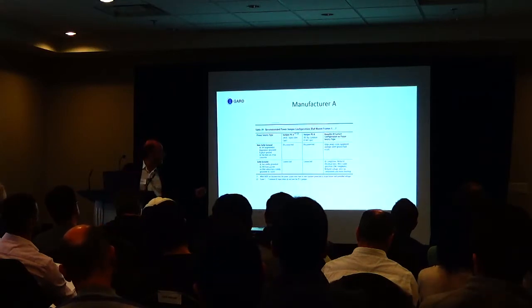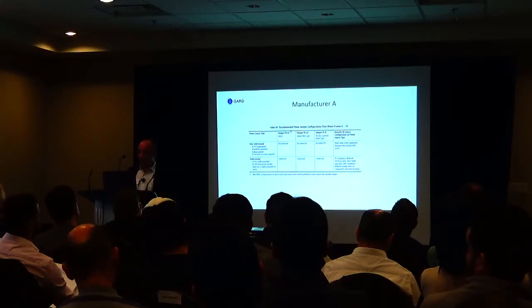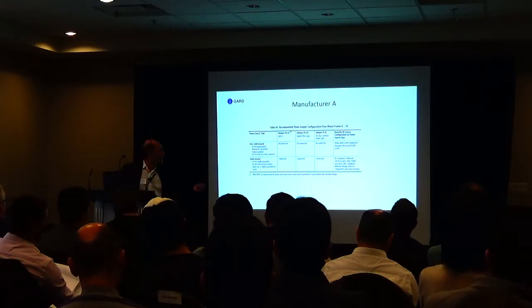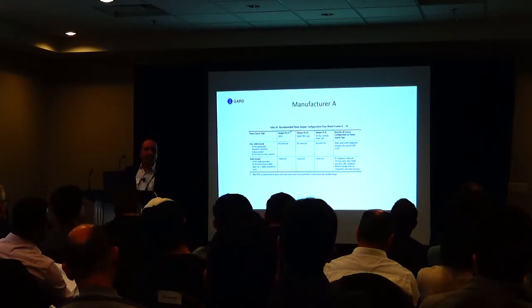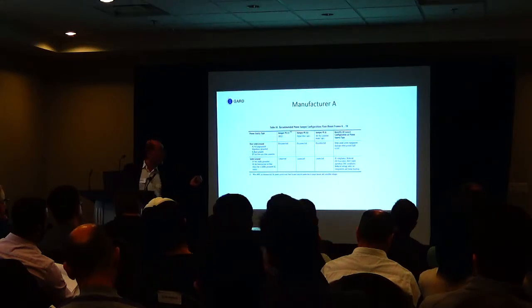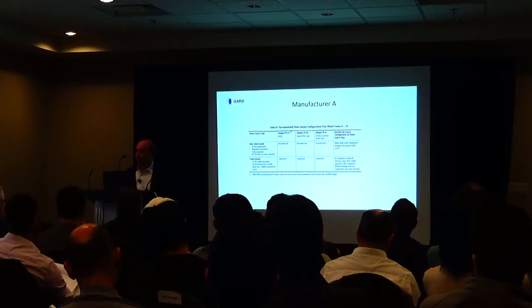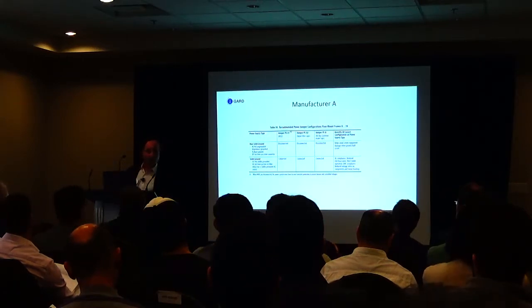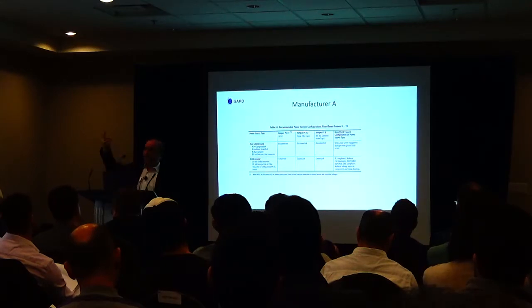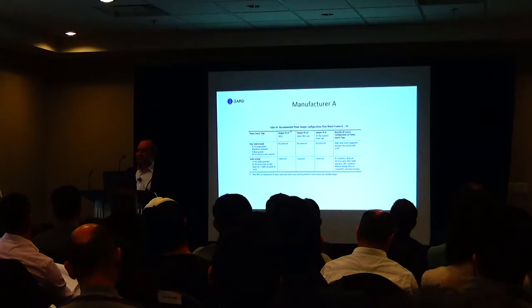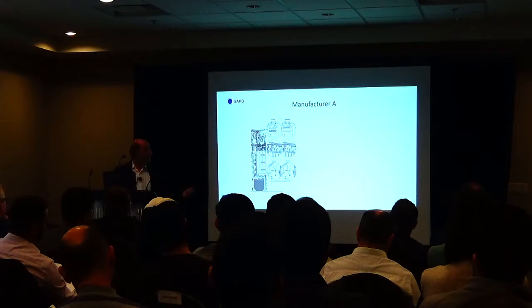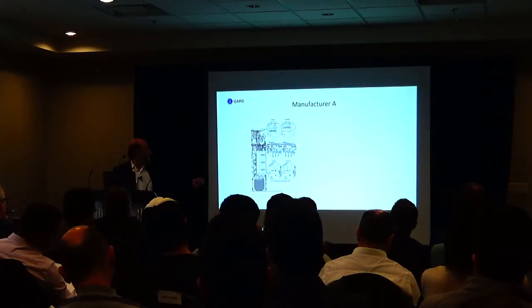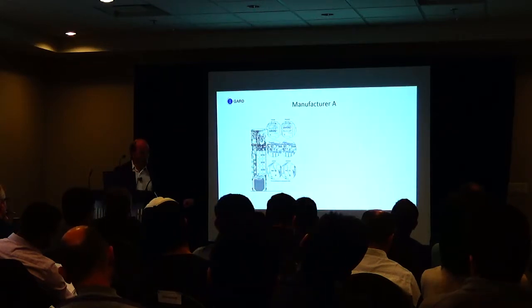And the DC bus mode caps. Same manufacturer, 3 jumpers this time. MOV, always have to disconnect the MOV because the MOV is not compatible with a B-phase grounded system or when 2 of the phases are elevated in potential. And that's what happens when you have an ungrounded system or a resistance grounded system. 2 of the phases are going to be elevated. Not always A and C. Sometimes it could be A and B. Sometimes B and C. And they even show you where the jumpers are. Connected, disconnected. Connected, disconnected. Connected, disconnected.